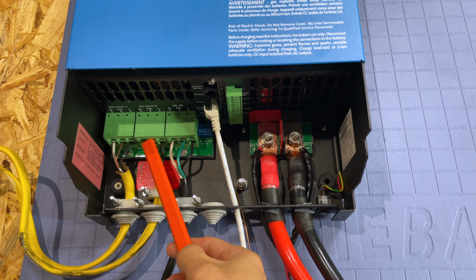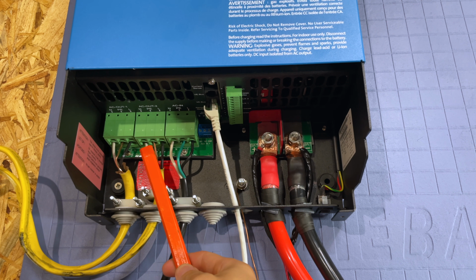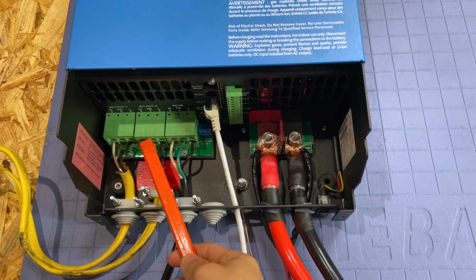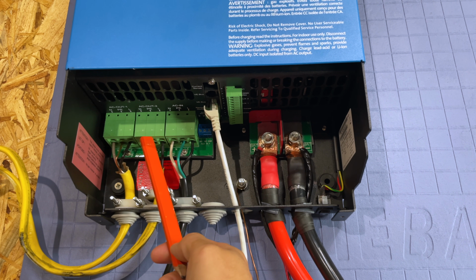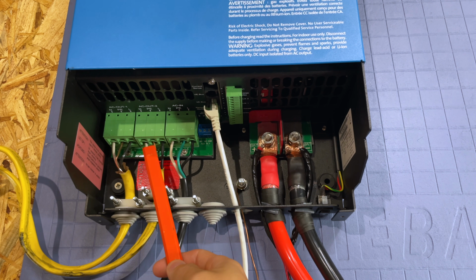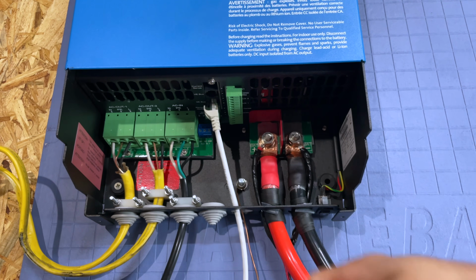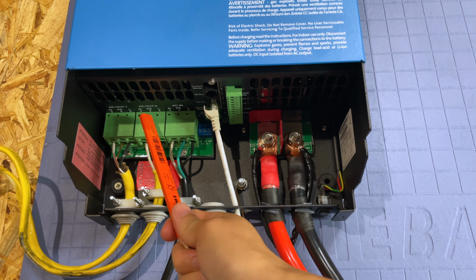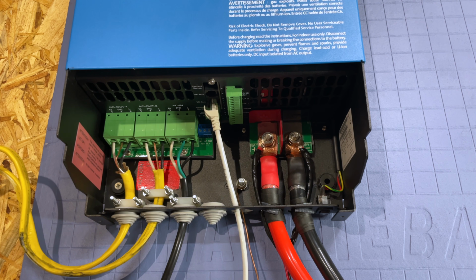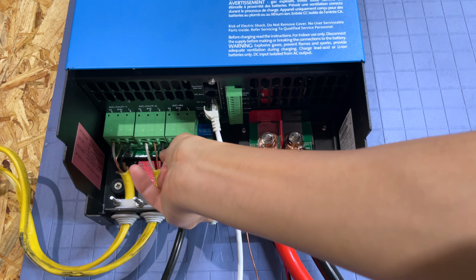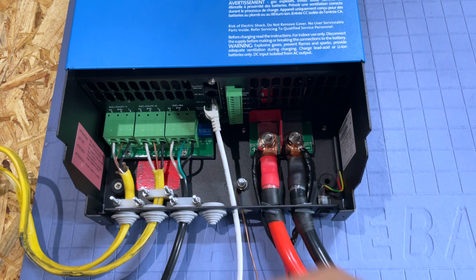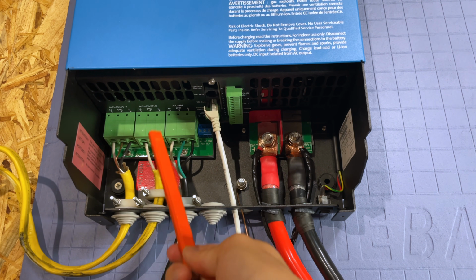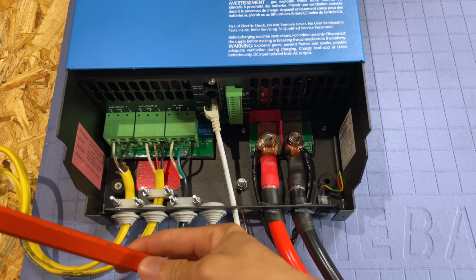You have to use either a flathead screwdriver, or in my case, I also used a framing nail to press in that port to relieve the pressure on the spring that clamps down on the cable. So this is a friction type fit clamping system. It's not like you screw and it clamps together. There's a spring-loaded clamp in here and it clamps down on the wire, right? And even on these. So if you pull it, do a solid pull test, and it's not going to go anywhere. But it is a pain to work with when you're removing stuff.